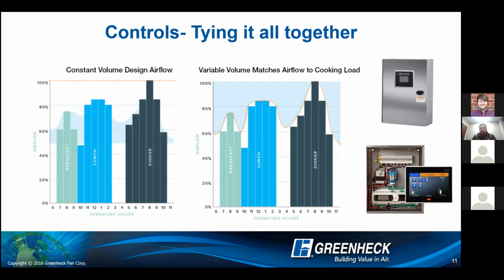The final thing to note when it comes to specifying controls is that I see a lot of times that folks are asking for fan and light switches on their controls. Just know, and I think this image shows it, that the industry has moved to whether you have a constant volume system or a variable volume system, you're actually going to have a touch screen that comes with that. We no longer, Greenheck and most manufacturers no longer use toggle switches. It's better for the manufacturing process to keep that LCD touchscreen, whether you have constant volume or variable volume.